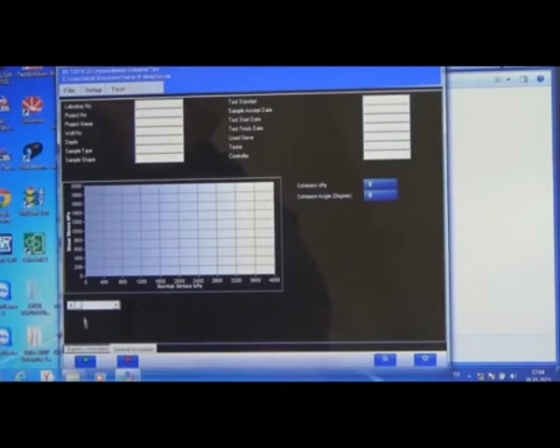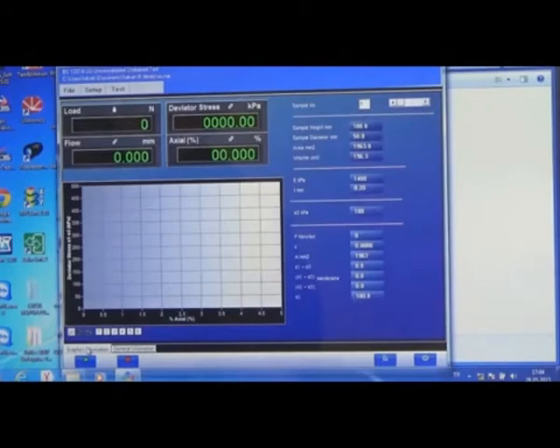Now the first tab on the left side is the graphics information. On the right side there are some boxes that need to be filled about the specimen. Again, we have used a 50 millimeter diameter sample, which has a height of 100 millimeters. That's why we are entering 100 millimeters for the sample height and 50 millimeters for the diameter, and as you can see, the area and the volume are automatically calculated.